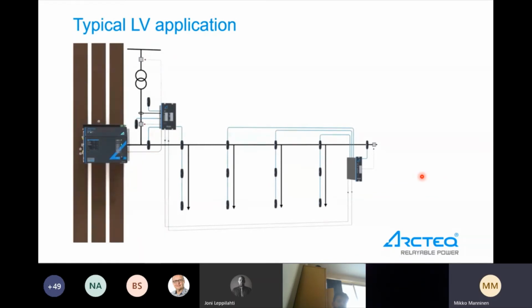And a typical LV application is the quenching device very close to the breaker, the incomer breaker, and then this is done with the point sensors. Point sensors are typically for the bus bar, and in low voltage it's quite often open, with no segregation and no compartments between bus bar sections. So few sensors for the bus bar, and then for the feeder breakers and cable ends. And this is a quite typical application.